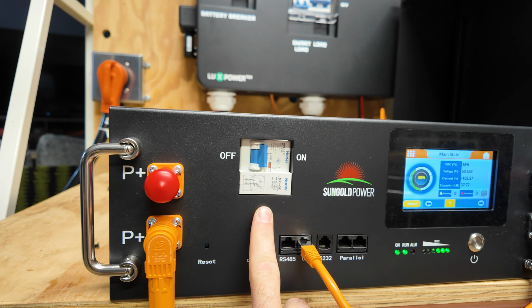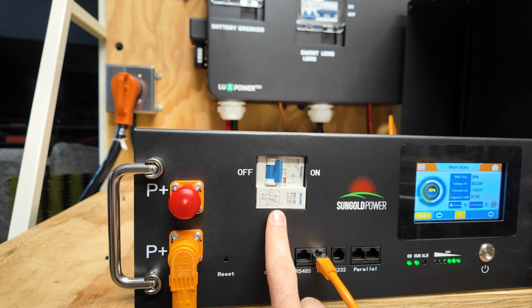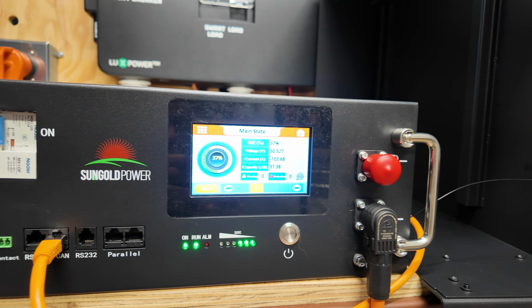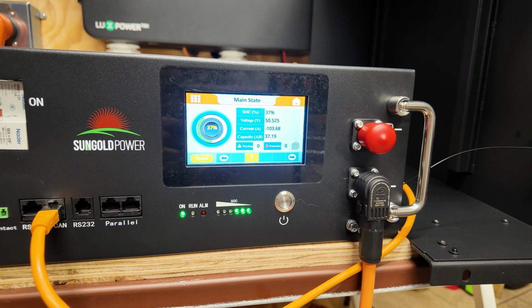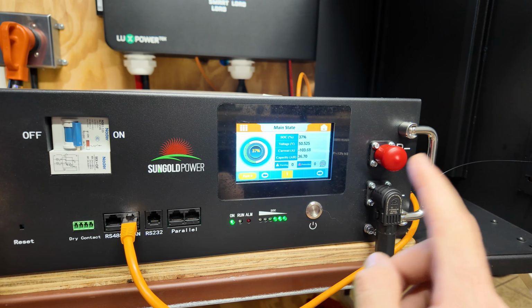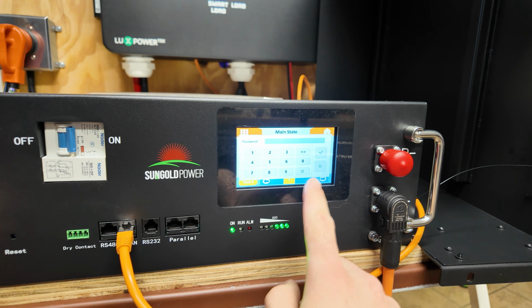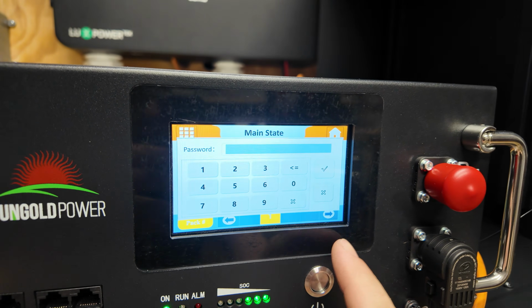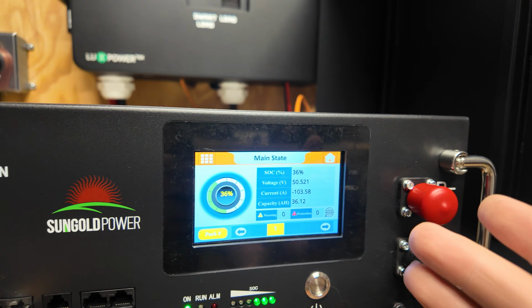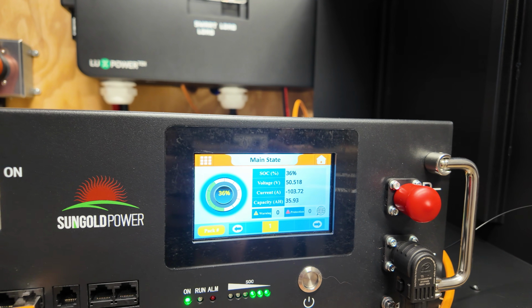For those curious, the breaker's rated at 125 amps, which is why we haven't tripped this. Now, as far as tripping the 100 amp cutoff or the 95 amp cutoff, I would like to go into the BMS and see what it's actually set to, but there's a password and I haven't figured that out yet. So if I can figure that out, I'd like to go into the BMS and see what they actually have the high current cutoff set to.